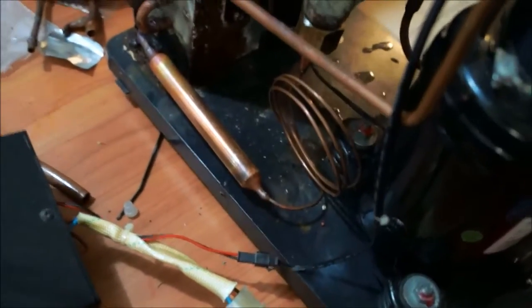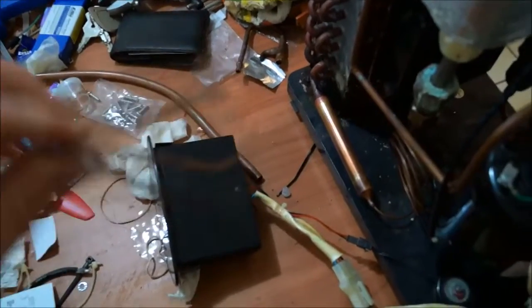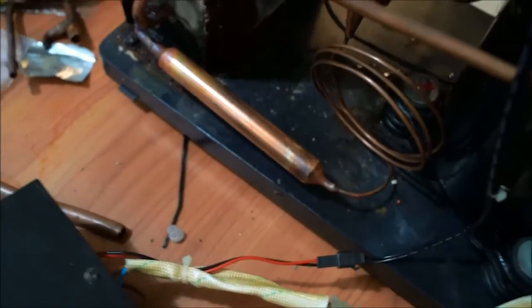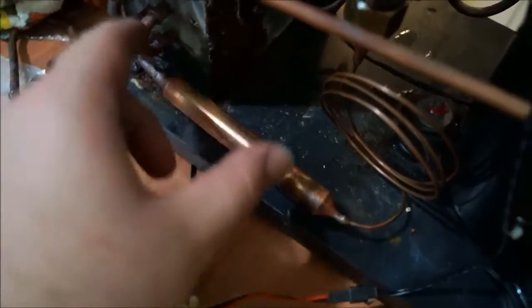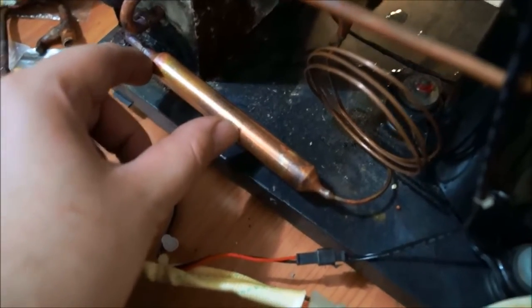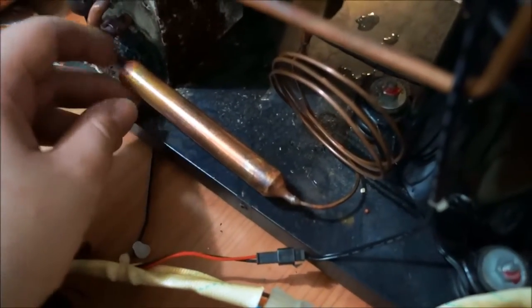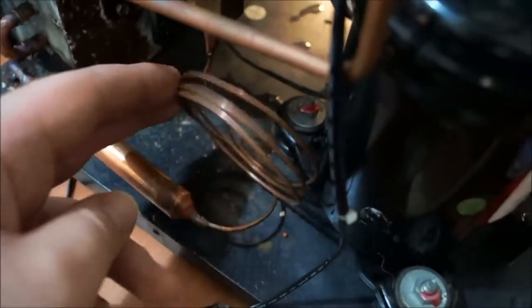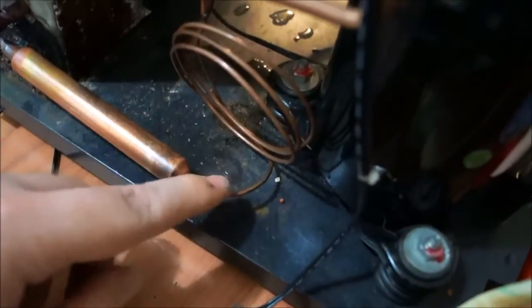So what I've had to do is this is all actually new. I bought a new filter dryer off eBay which is actually a fair bit longer than the old one, almost double the length. That's a new filter dryer, new capillary tube as well. I just cut the old one off right here, brazed this one on, brazed in a new capillary.